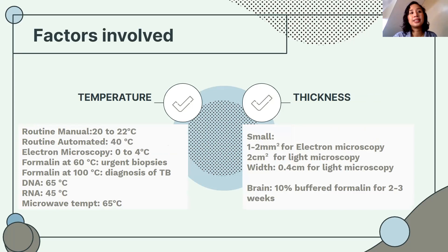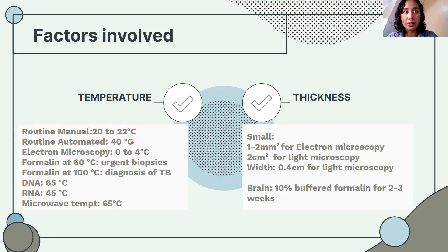Temperature: in routine fixation, we process at ambient or room temperature of 20 to 22 degrees Celsius. However, in automated tissue processors such as fluid transfer processors, temperature is set at 40 degrees Celsius. Subjecting tissue to heat hastens the penetration of formalin — at higher temperatures, molecules move faster and can penetrate more easily.